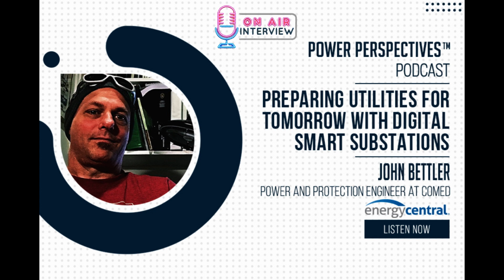And MMS is basically a SCADA protocol. Most of the United States is probably using DNP3 as most people's bread and butter SCADA protocol. The issue with DNP3 when you go to a 61850 substation is kind of like having a dictionary from 1975. If I gave you a dictionary from 1975, you'd say, yeah, this will help me write my term paper, but it's lacking in some regards because it won't have modern terms. Like it's not going to have laptop. It's not going to have cell phone in there because those weren't really things in 1975.